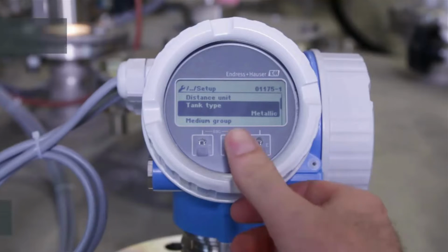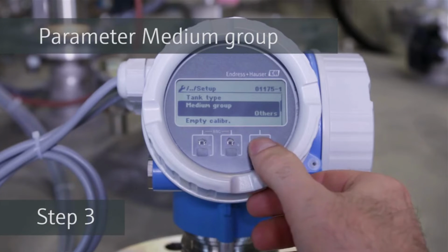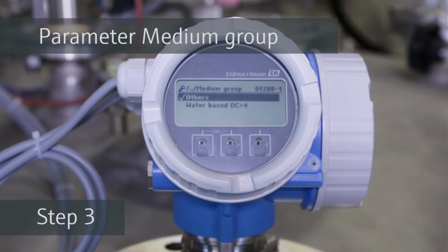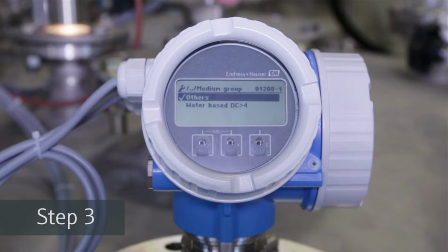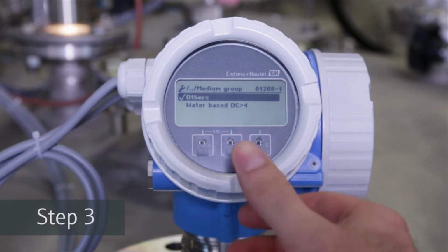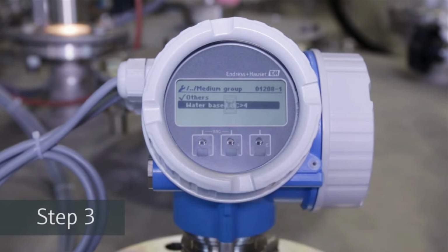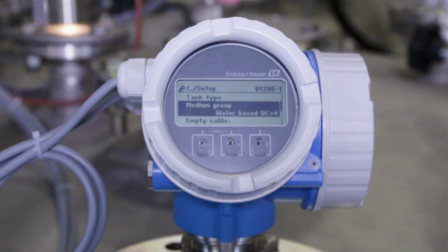For instruments measuring levels in liquids, determine the medium group to be measured in the next step. There are media with DC values smaller than 4, for example oils. We select the option Water-based, used for media such as acids, brines or solutions, which have a DC value larger than 4.